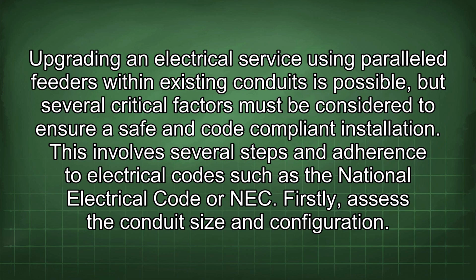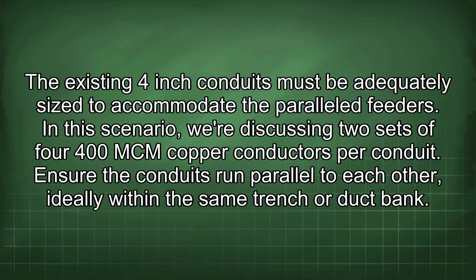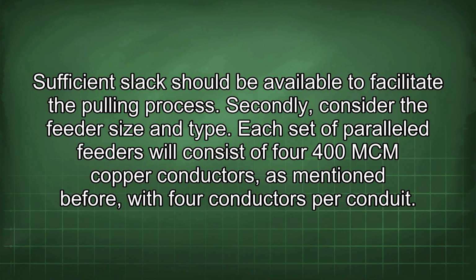Firstly, assess the conduit size and configuration. The existing 4-inch conduits must be adequately sized to accommodate the parallel feeders. In this scenario, we're discussing two sets of four 400 mcm copper conductors per conduit. Ensure the conduits run parallel to each other, ideally within the same trench or duct bank. Sufficient slack should be available to facilitate the pulling process.